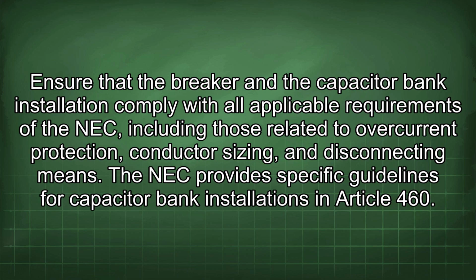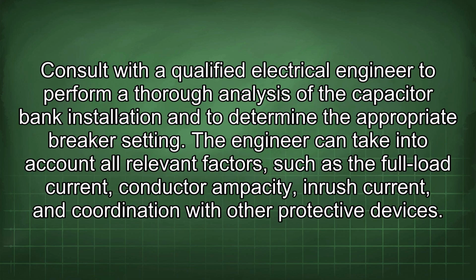Ensure that the breaker and the capacitor bank installation comply with all applicable requirements of the NEC, including those related to overcurrent protection, conductor sizing, and disconnecting means. The NEC provides specific guidelines for capacitor bank installations in Article 460. Consult with a qualified electrical engineer to perform a thorough analysis of the capacitor bank installation and to determine the appropriate breaker setting. The engineer can take into account all relevant factors such as the full load current, conductor ampacity, inrush current, and coordination with other protective devices.